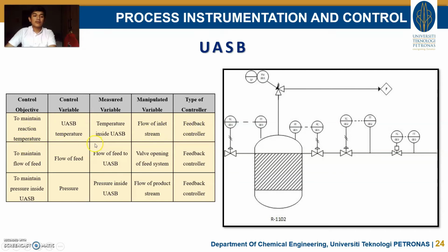The next one is to maintain flow of feed. The control variable is flow of feed. What we measure is the flow of feed to UASB, and the manipulated variable is valve opening of feed stream. And the last one is the pressure. So we measure the pressure inside UASB. The manipulated variable for this one is flow of product stream. So for UASB, we install 3 controllers, which is temperature controller, pressure controller, and also flow controller.